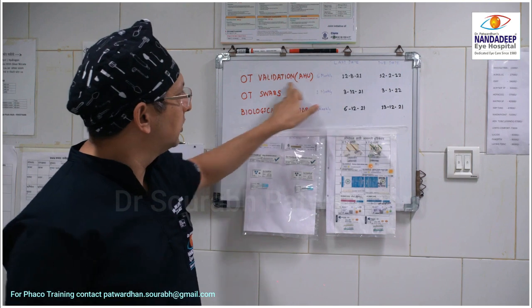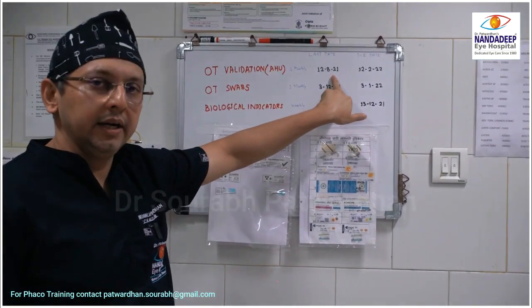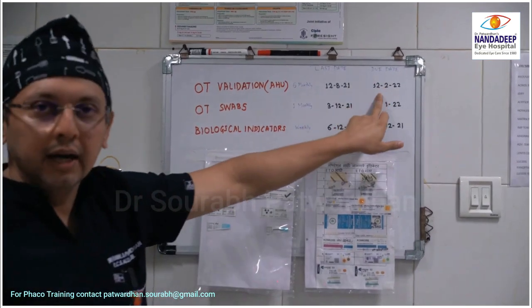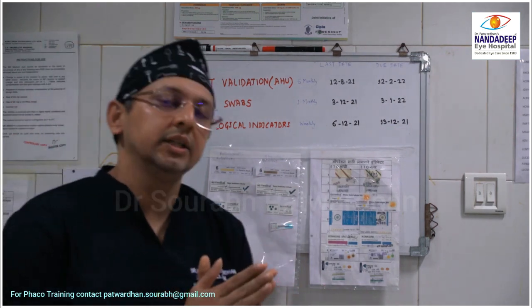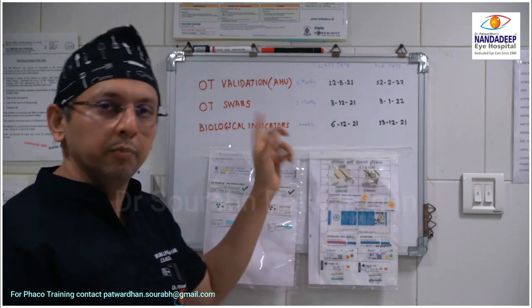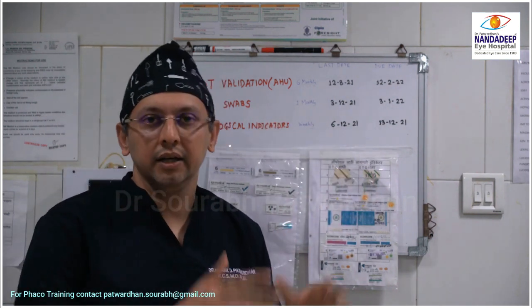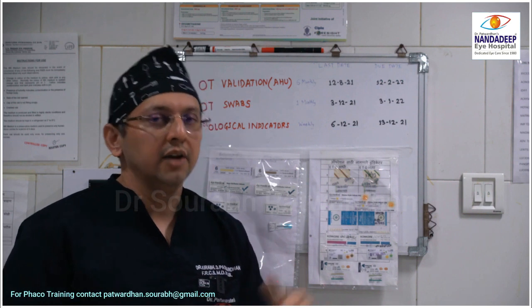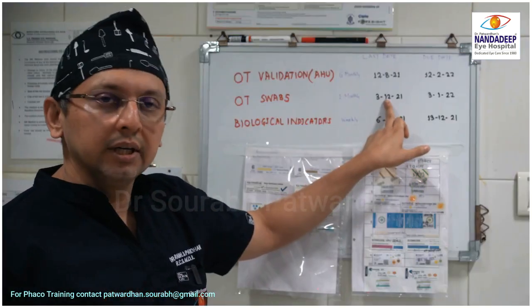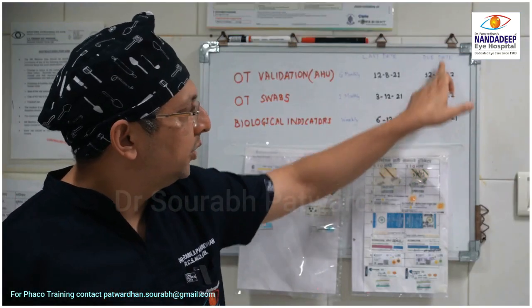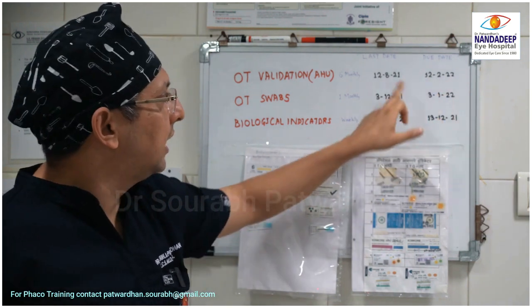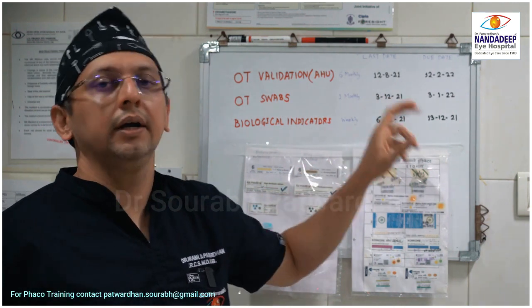The first thing is OT validation. You can see this is the last date when it was validated and this is the due date. The moment I walk in, I should know whether the OT has been validated. This validation is mainly for the air handling units with HEPA filters. If the air handling unit is not properly validated and maintained, it is as risky. You can see the due date is within a month, and if the last date has not been changed, I know it has not been done.